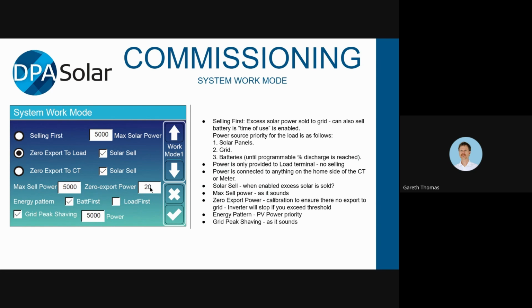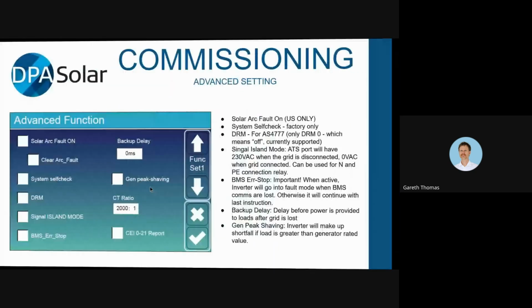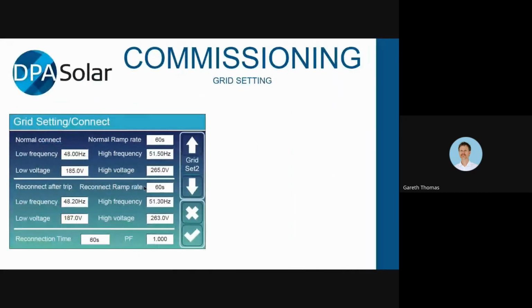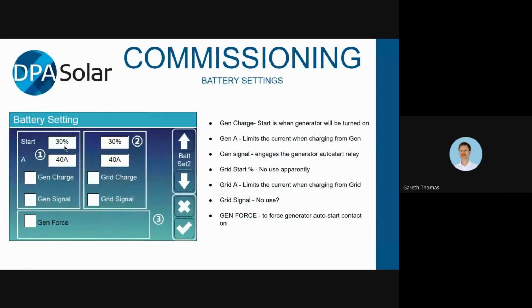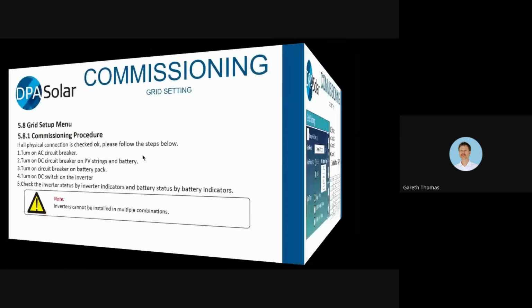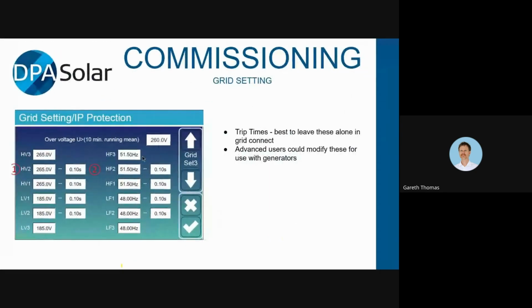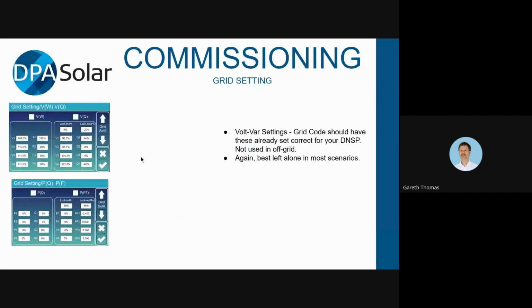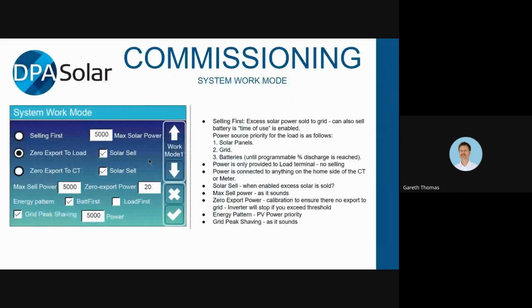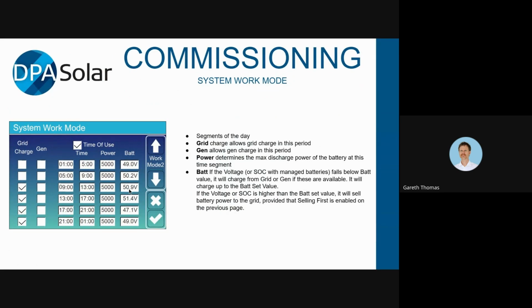So if we go back through those again, just to make this clear, if you don't have that set up, it's only going to start charging from the generator when it gets down to 30%, and it will just charge all the way up to 100%. But if you have time of use enabled, it will charge up to whatever you've got set for that time period. So instead of charging up to 100%, it will charge up to whatever you've got as a battery voltage or percentage in time of use.